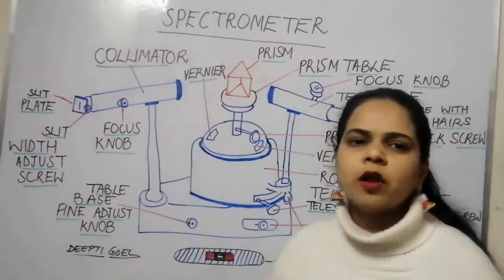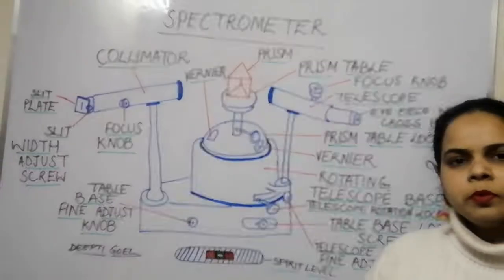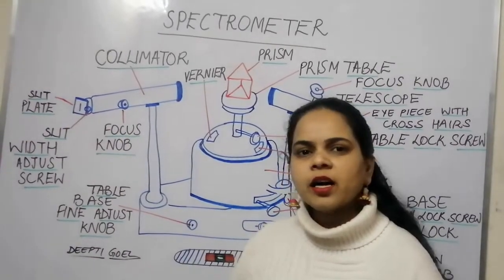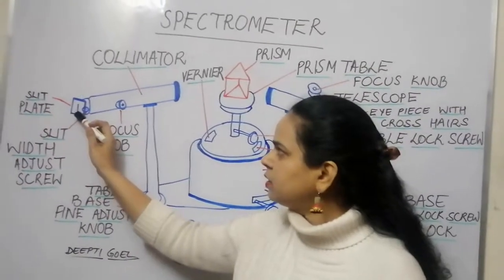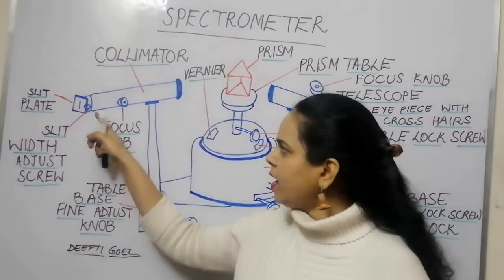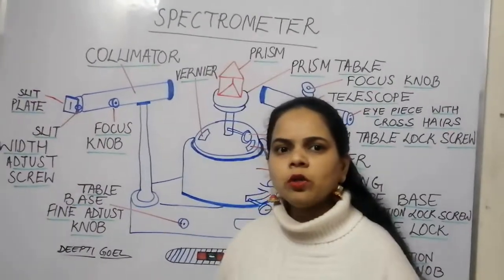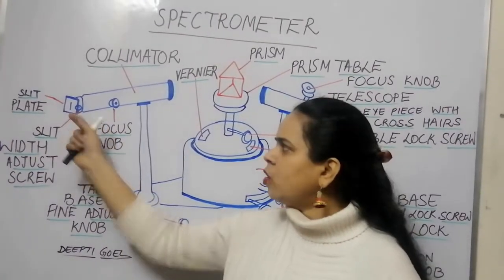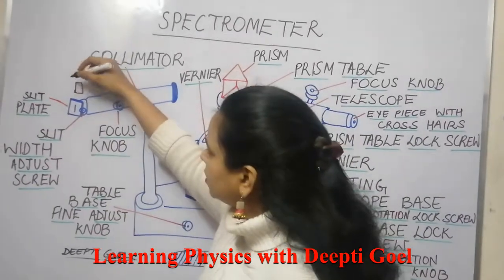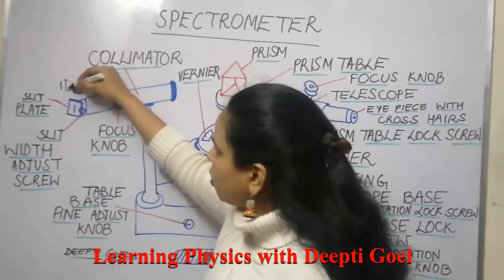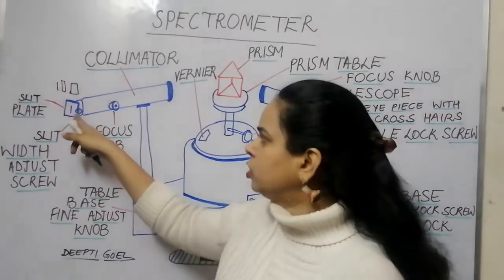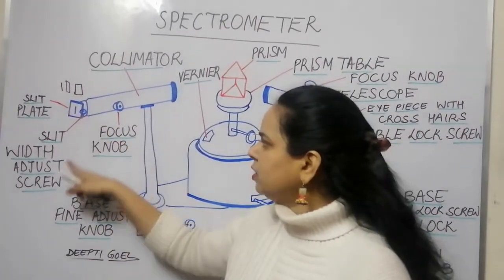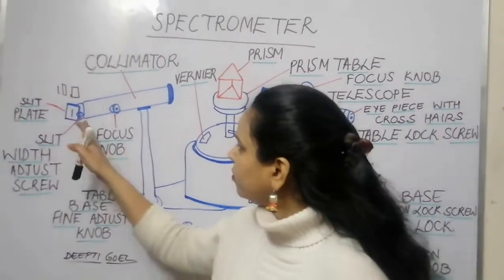The collimator is a tube consisting of two convex lenses. Attached to it is a slit plate with a rectangular slit and a slit width adjust screw. By opening or closing this screw, the slit width can be increased or decreased according to our requirement.